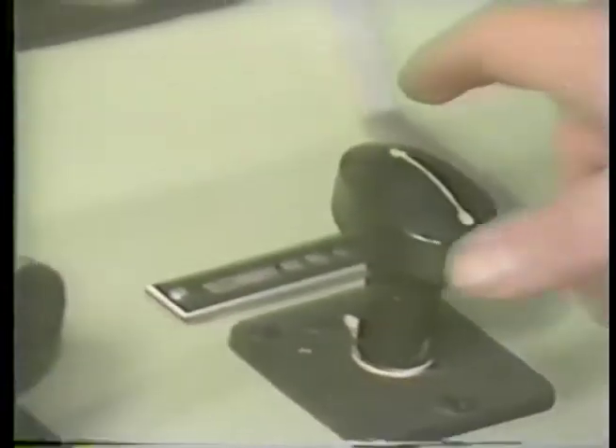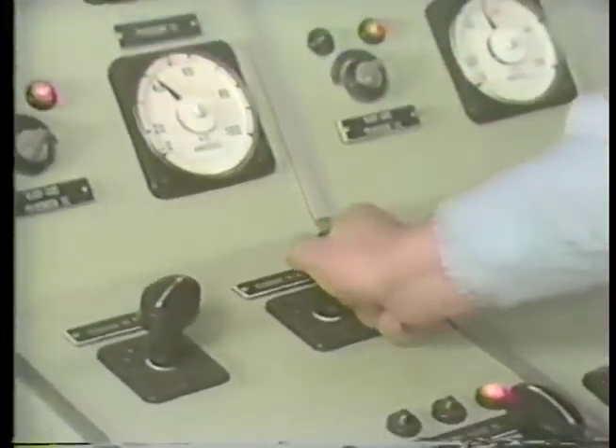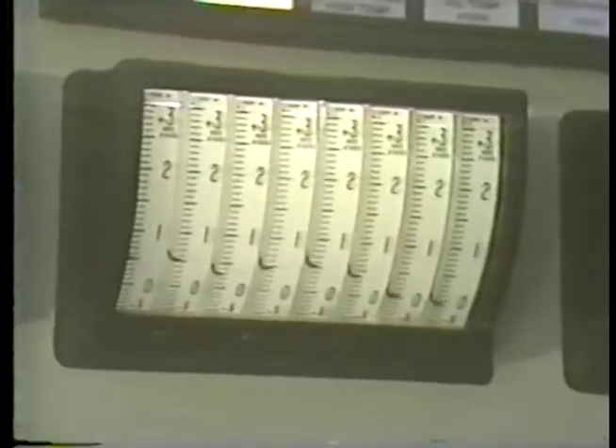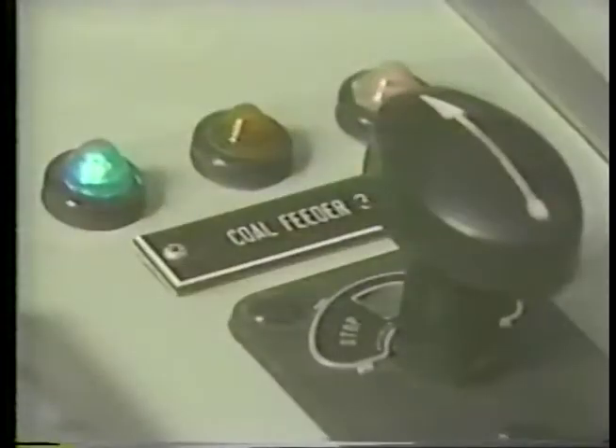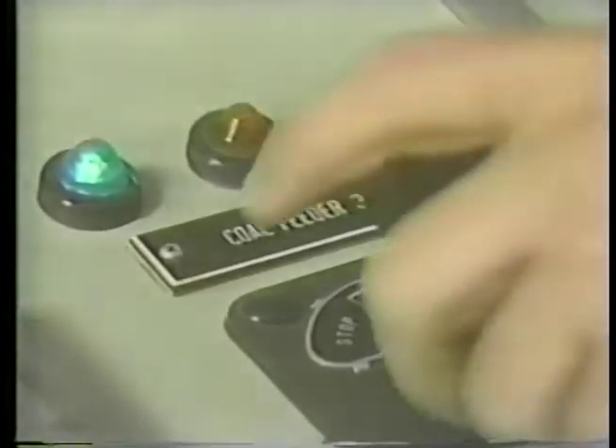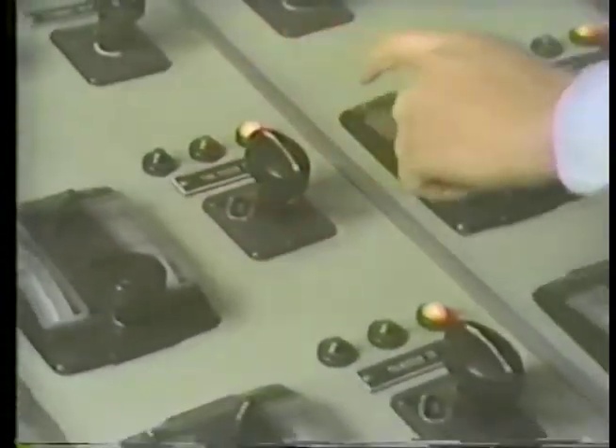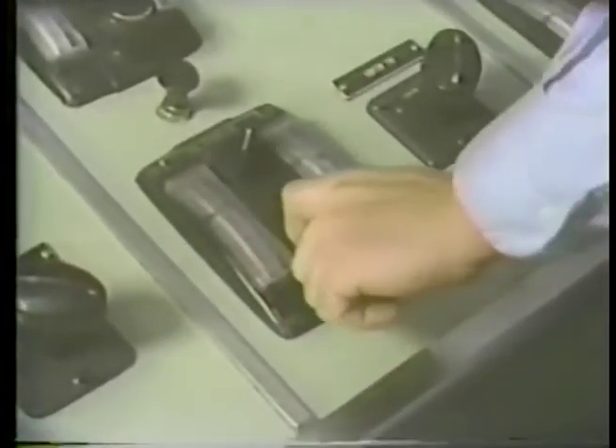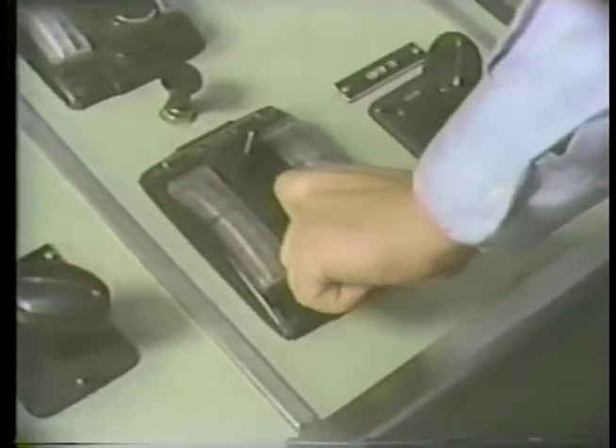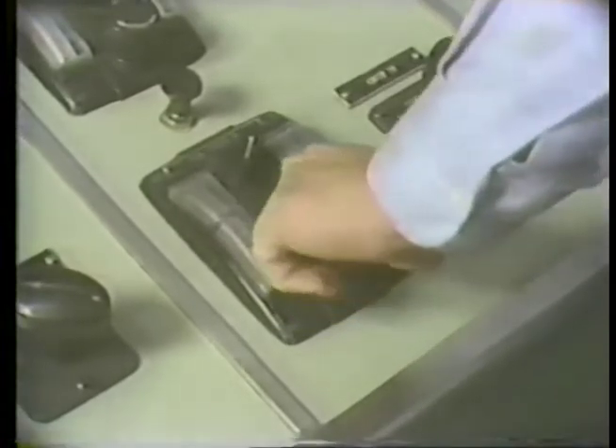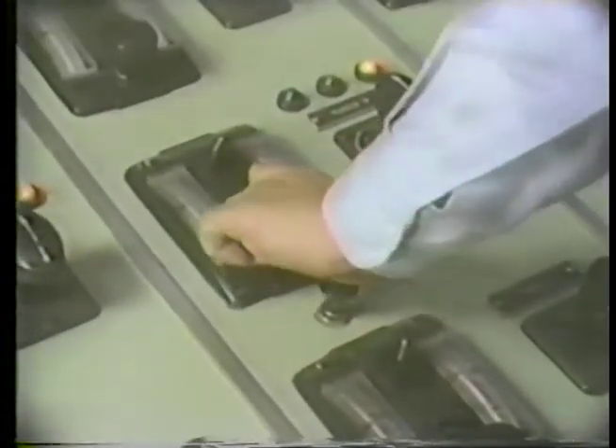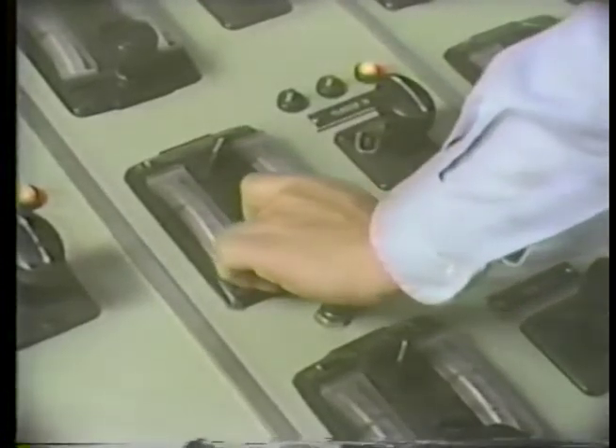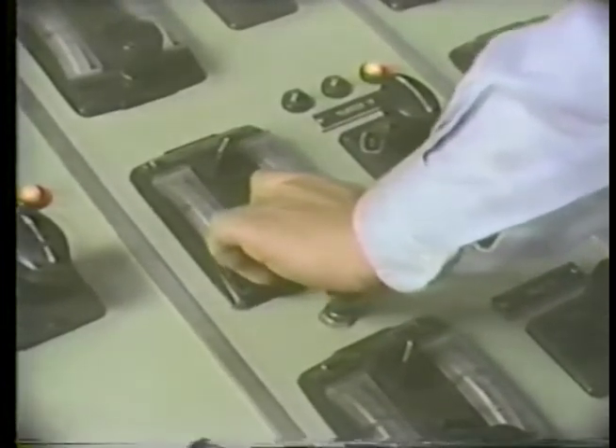With the pulverizer operating, the operator next adjusts air dampers to direct secondary air into the boiler. This is to ensure sufficient air for complete combustion when fuel is supplied. He next starts the appropriate coal feeder to supply the fuel for combustion. With the feeder on, he adjusts the flow rate according to his operating procedures. With fuel going to the pulverizer, the operator now adjusts the primary airflow to the pulverizer to first dry the pulverized coal and then transport the coal to the burners.